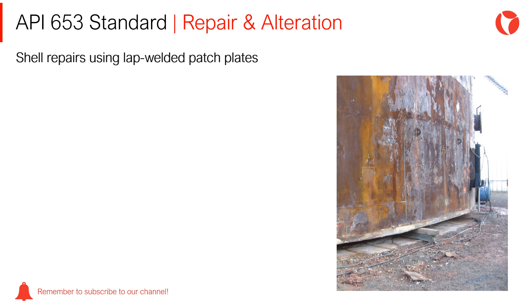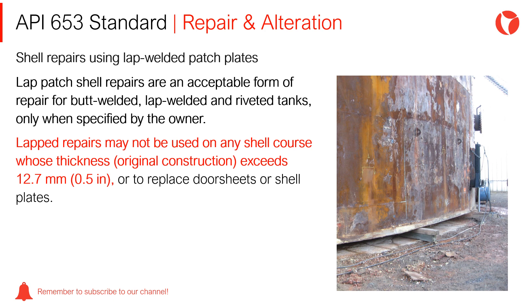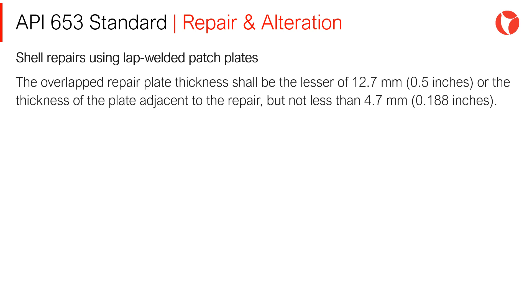Another alternative when it comes to repairing a tank wall are patch plates. Lap patch shell repairs are an acceptable form of repair for butt-welded, lap-welded, and riveted tanks, only when specified by the owner. Lapped repairs may not be used on any shell courses whose thickness exceeds 12.7 mm, or to replace door sheets or shell plates. The repair material must meet the requirements of the current standard and API 653. The overlapped repair plate thickness shall be the lesser of 12.7 mm or the thickness of the plate adjacent to the repair, but no less than 4.7 mm.